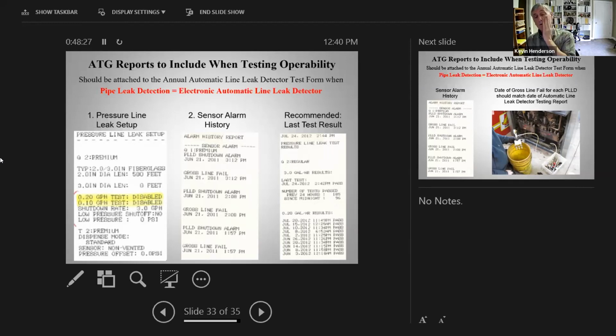And I'm going to tell you something, if you've ever done functionality testing on PLLDs, it is not easy to do in some cases. In our experience, getting electronic line leak detectors to actually go into alarm when we have a 3 gallon per hour simulated leak, more times than not, it will not go into alarm. We cannot get them to go into alarm.